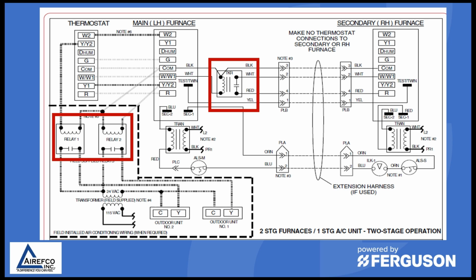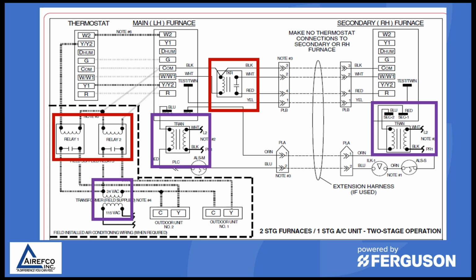Another thing that you need to be very concerned about when installing twin furnaces are the transformers. Each furnace has a transformer, and many kits will direct you to install a field supplied transformer to power the relays that you're using. If they do this, you will have to make sure that your transformers are wired correctly, and if they need to be phased together, follow the manufacturer's instructions to do this so you don't blow fuses when you power up the systems.